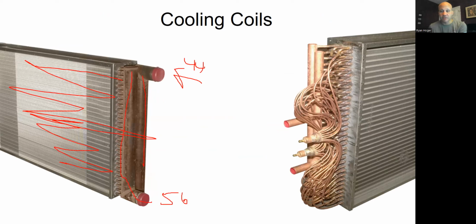But if it's DX, direct expansion, meaning there's refrigerant in the coil, then instead of having a header like that, you'll have all these distribution tubes. And this one happens to be a 2-circuit coil, right? So there's a supply and a return for each of the circuits. So instead of one big header, you'll see all these little skinny distribution tubes. And that's a quick visual way to know if you have refrigerant in the coil or if you have water in the coil. And if you have refrigerant, you're going back to module 2 for your heat pump solutions. If you have chilled water, then you're on this module.